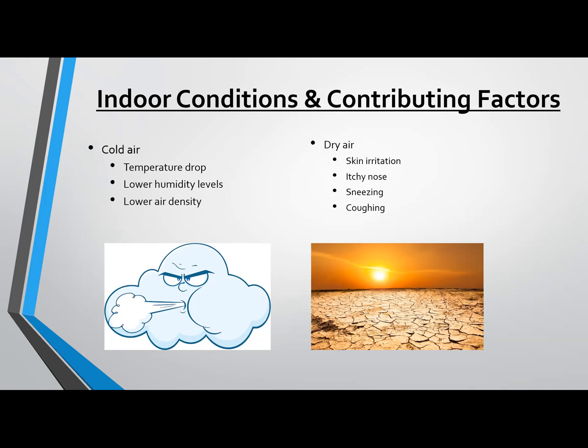With cold air, most of our facilities are designed for between 72 and 74 degrees as standard. But as air gets colder, the temperature drops and humidity levels inside buildings drop as well. Sometimes facilities kick back to the mid 60s when unoccupied and then reheat based on their automation system when in occupied mode. As that air gets colder, humidity drops, and the density of the air drops too, making it a little thinner. That comes into play as we get further down the road.